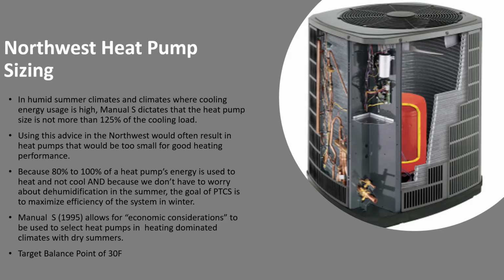125% advice we get out of Manual S, we'd often end up with tiny heat pumps that use lots of electricity. In most parts of the Northwest, 80% to 100%, maybe less on the coast, of heat pump energy is used to heat and not cool. So we're much more concerned about the efficiency in heating than we are in cooling.